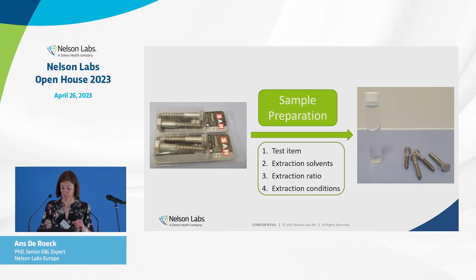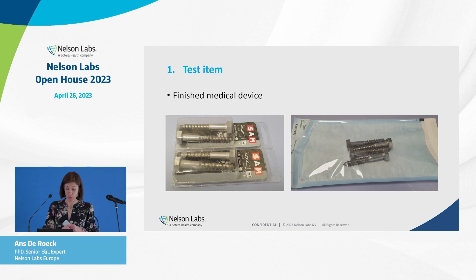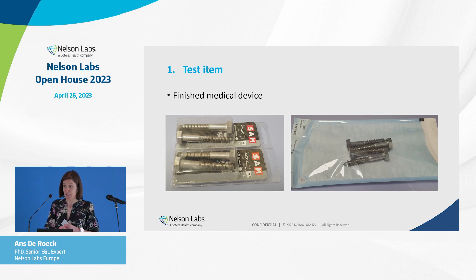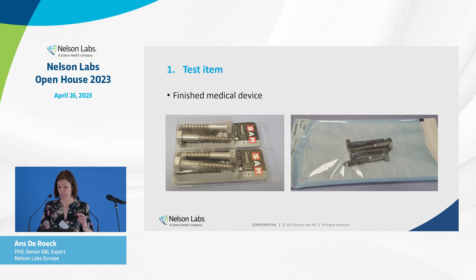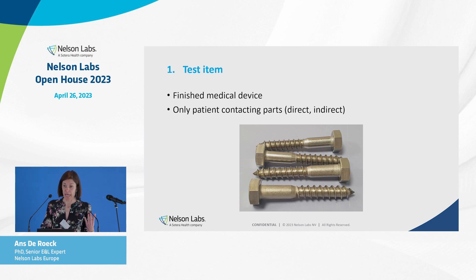The first step is sample preparation — we start with a medical device and end with an extract. We always receive the test item from our sponsors. Two remarks: we always test the final finished medical device, so if the device is packed or sterilized we need to receive it packed or sterilized. And we only test the patient-contacting parts — direct or indirect — non-patient-contacting parts don't need to be tested.